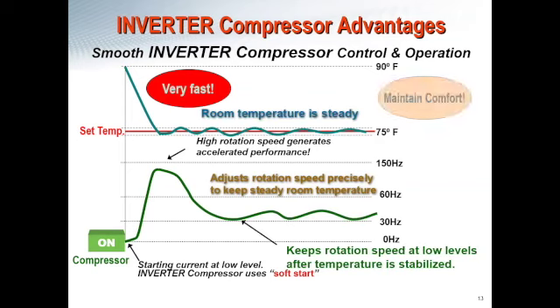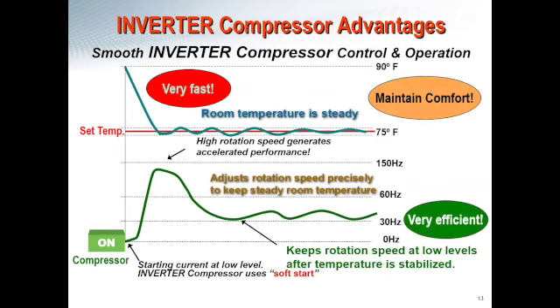So what this allows us to do is modulate that compressor, not go with the typical on-off control, and actually hug that set point significantly more closely. Because you're not kicking on, kicking off, you can keep a deadband of half a degree above or below that 75 degree set point, and really modulate to keep the control in the space, keep the temperature in the space very tight.